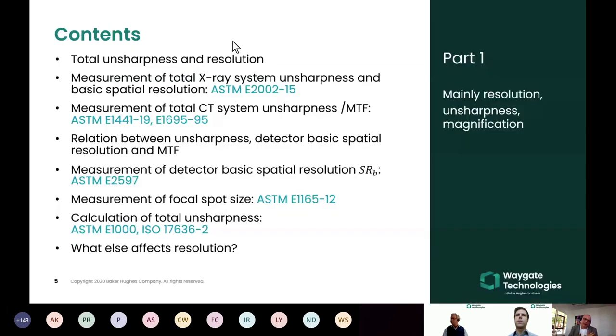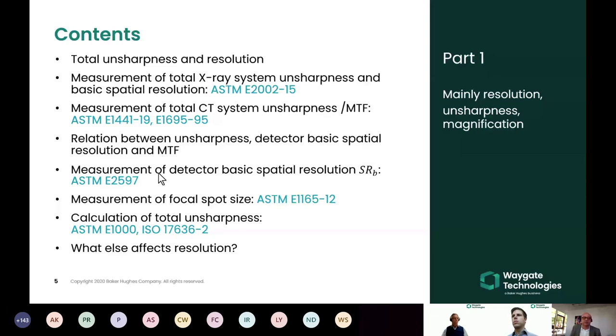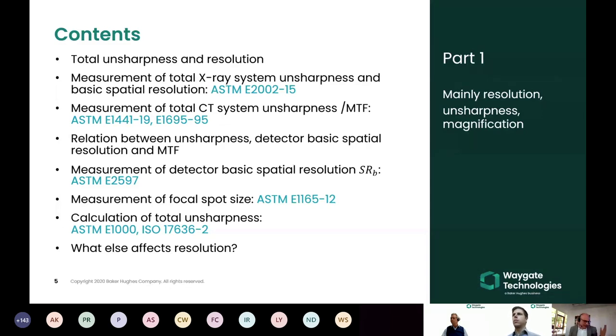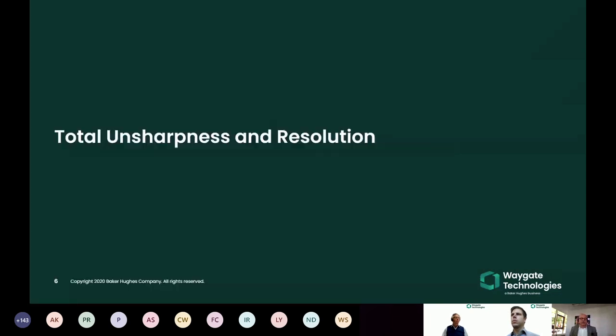I'll keep a path along the standards because this is the best way to have well-defined quantities. After a short introduction, I'll describe how the total unsharpness of an X-ray system is measured by standard ASTM E2002, the equivalent for CT, the relation between unsharpness and detector spatial resolution, how the detector basic spatial resolution is measured, how we measure focal spot size, and how you can calculate the expected sharpness of any X-ray system.